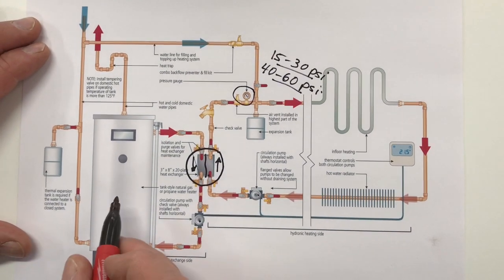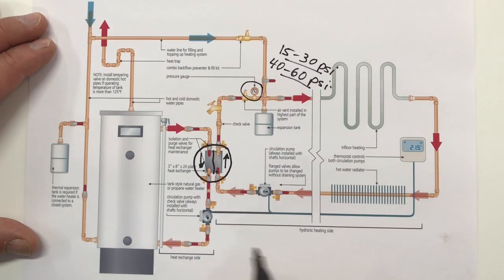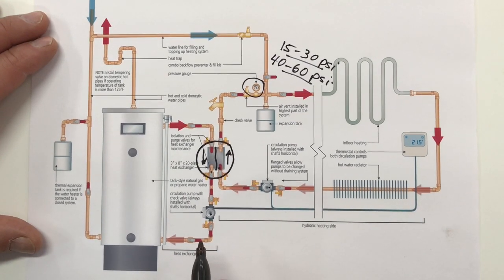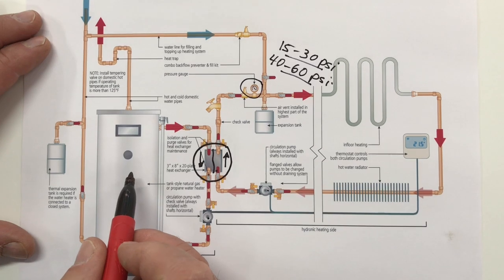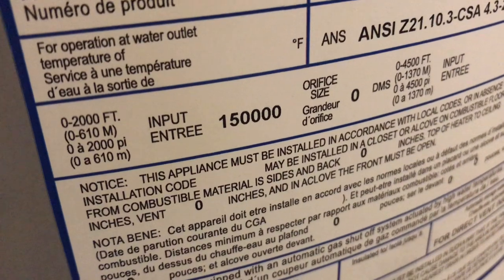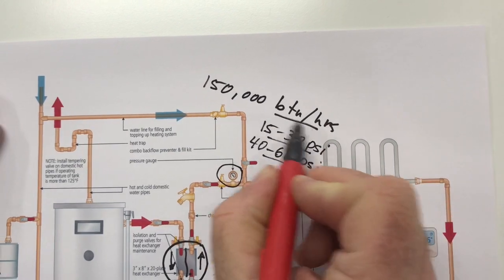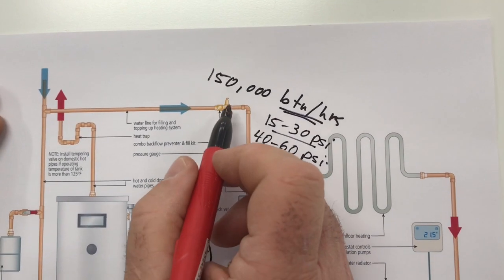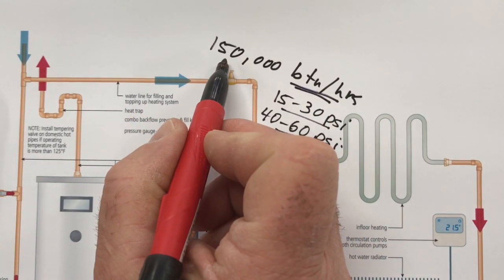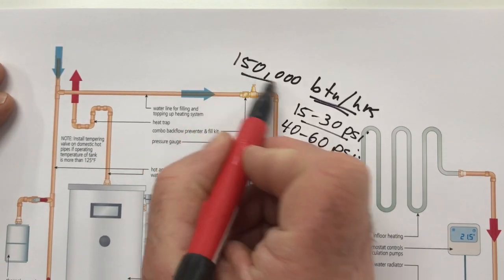So if a system like this is such a good way to power a hydronic heating system how come everyone doesn't use it? Well first of all the tank needs to be up to the job, it needs to have enough heat output. The tank I've installed at my own place has 150,000 BTU per hour input so that's plenty for heating needs as well as domestic hot water. Most standard tank style water heaters won't produce that much.